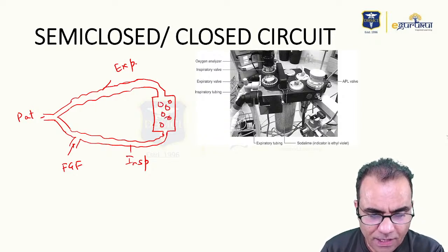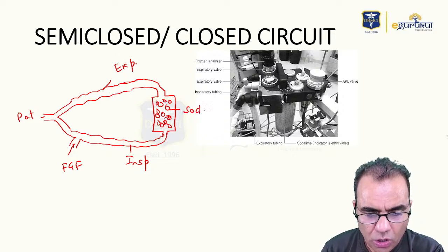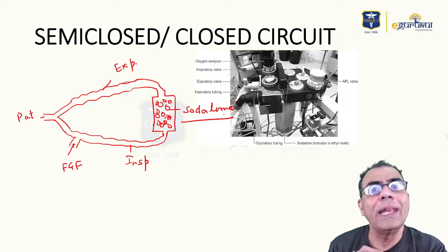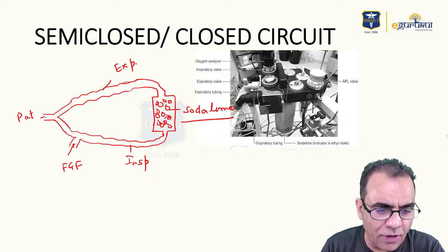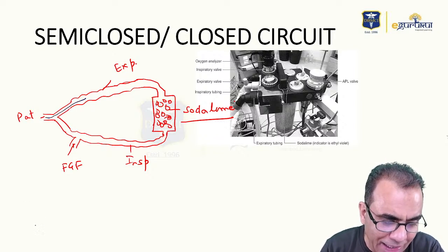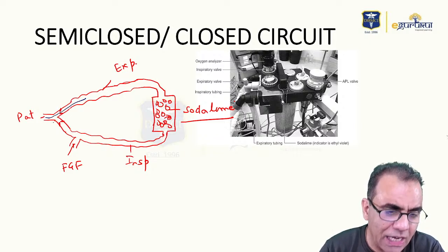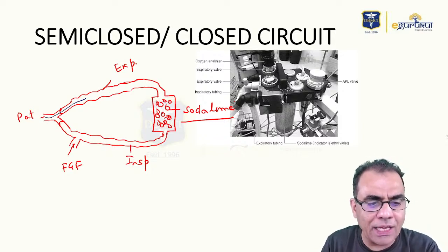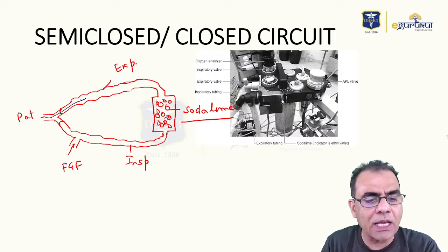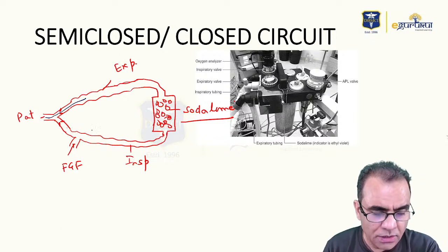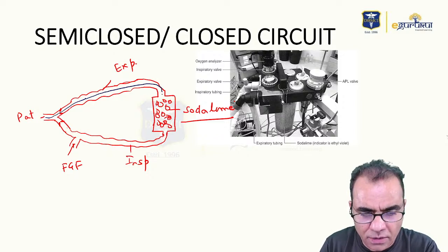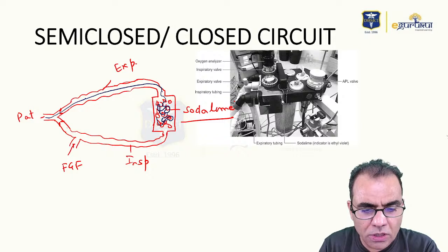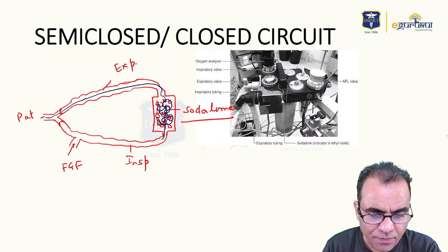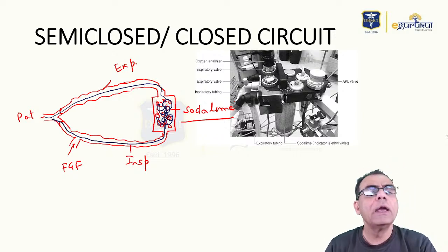And this is the canister containing soda lime. Now, the expiratory gases, which I'm showing here as the blue line, will pass through the expiratory limb and cannot enter the inspiratory limb because there are valves here. These are unidirectional valves, so expiratory gases cannot enter the inspiratory limb and inspiratory gases cannot enter the expiratory limb. The expiratory gases pass through the canister containing soda lime. What will the soda lime do? It will absorb carbon dioxide from these gases, and the same gases can be reused by the patient.